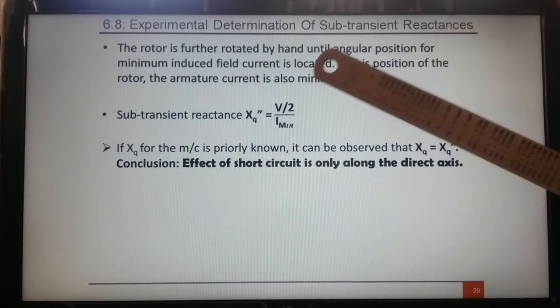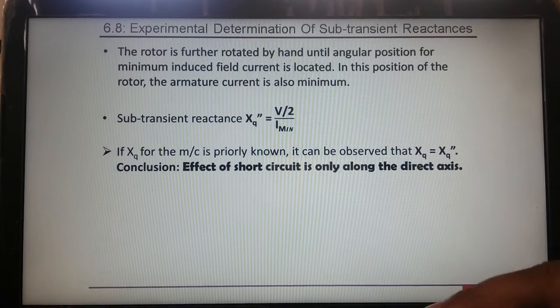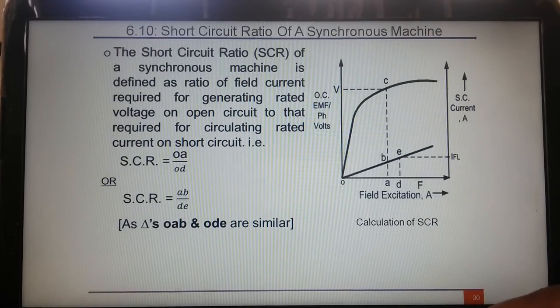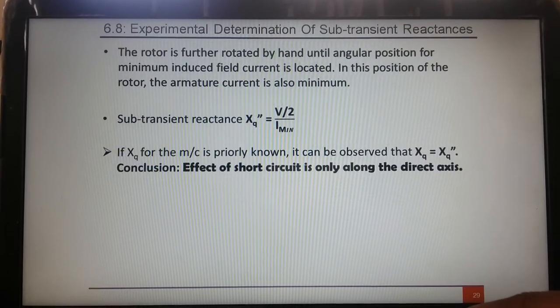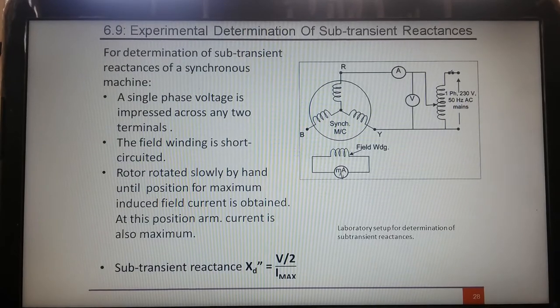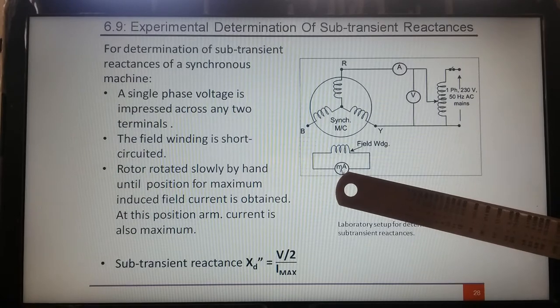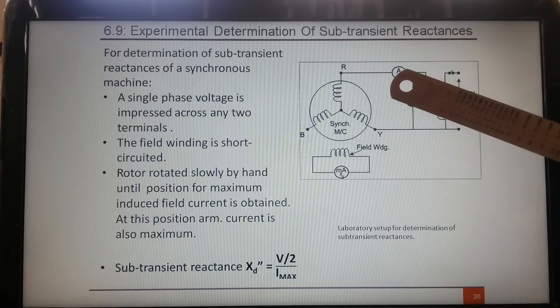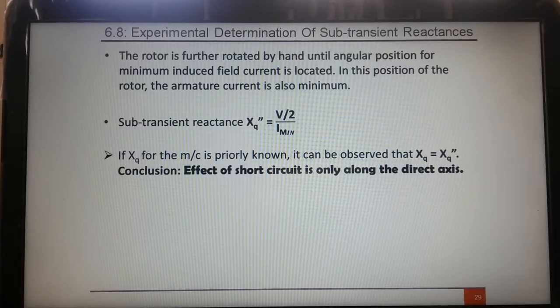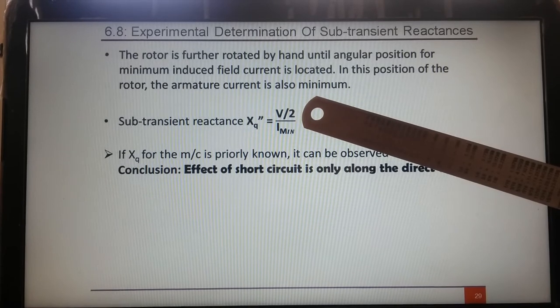Similarly, the rotor is further rotated by hand until the angular position for minimum field current is located. When the machine comes to the Q-axis, this current will be minimum, and correspondingly the armature current will also be minimum. That is why you get XQ double dash, which equals I minimum with voltage per phase V by 2.